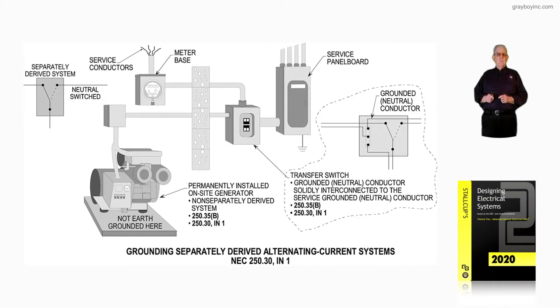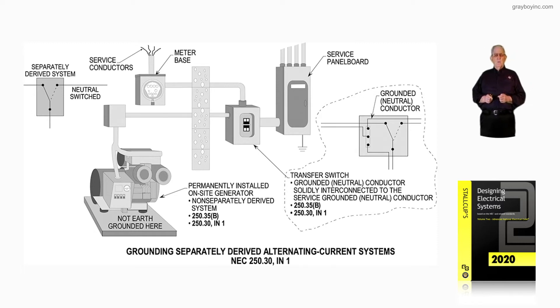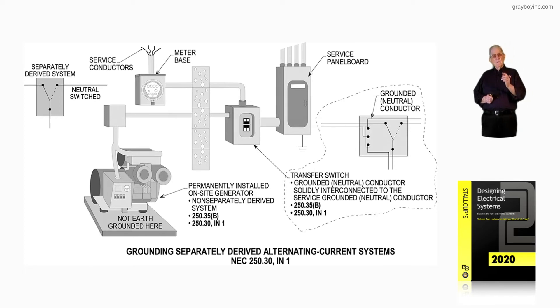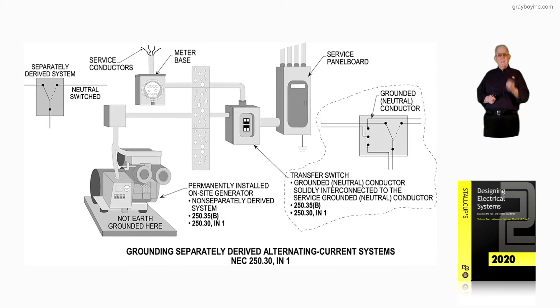This illustration further talks about grounding separately derived alternating current systems in accordance with NEC 250.30, and we're going to focus on the informational note listed there. Many times, even today, there are two questions I get quite often: how do you classify a generator as a separately derived system or non-separately derived system, and just exactly how do you classify the generator?